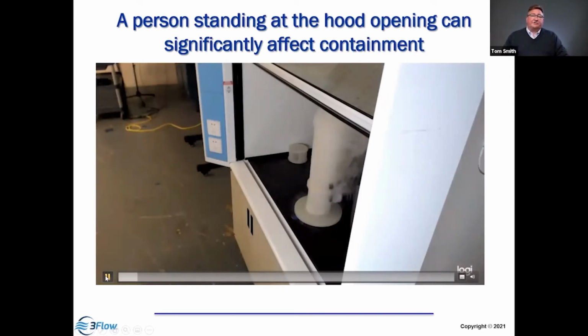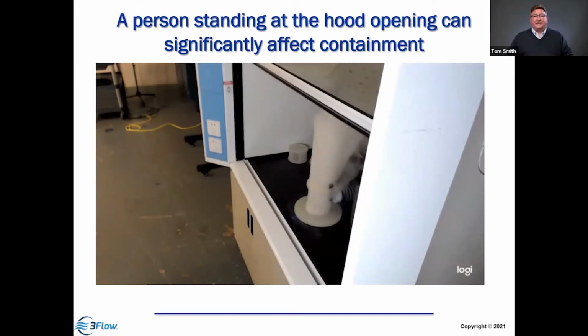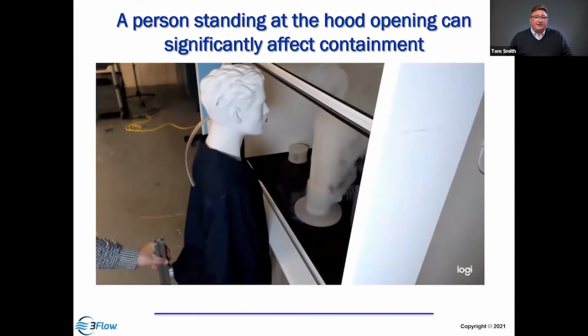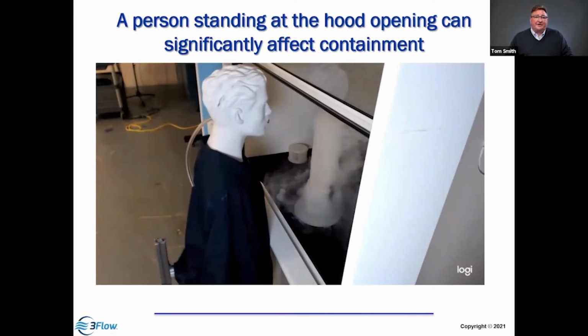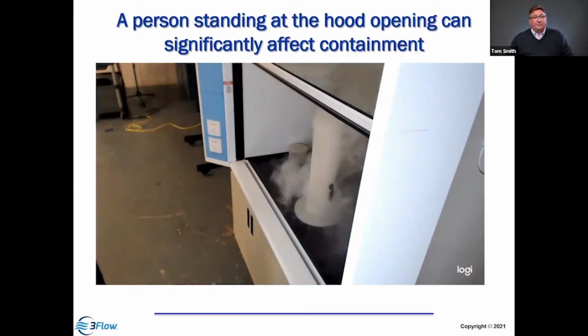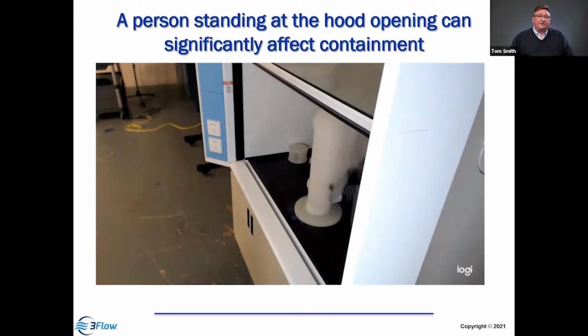So here we're generating smoke in the hood. There's no one standing at the hood. You can see it's containing properly. And all of a sudden we push our mannequin up to the hood and we see that it begins to disrupt the airflow patterns and we get some escape, right? So it was containing properly without a person standing in front of it, but the moment we put an obstruction in front, it begins to create those vortex eddies and escape from the hood occurs. And so when we move it away, you can see it draw out of the hood. And so movement near the opening is also very important. So we've demonstrated that a person standing in front of the hood can have a significant impact on hood containment.